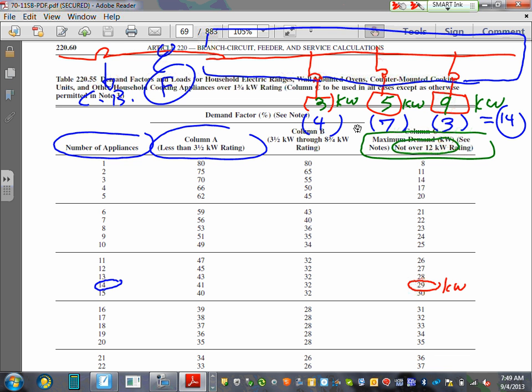Remember, the default is 29. Now I'm going to see, can I get lower than 29? Okay, so let's do it. I'm going to start with the first, I have 4. Here's 4. Can you guys see the 4? Here's the percentage. I need somebody to do the math for me, please. Multiply the 66, these are percentages, by 4 times 3. Anybody know why 4 times 3? I have 4 units. Each one of them is 3 kW. And the code says if you have 4 of them, you can cut them by 66. How much?